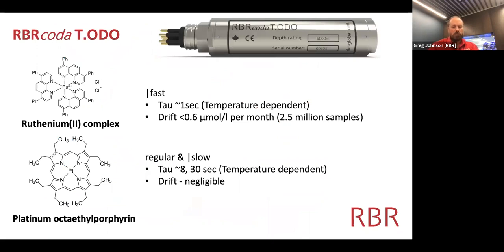So I'm going to draw your attention to the second grouping first. What is this luminophore? Well, this is a porphyrin complex. It looks a bit like a benzene ring. And this is the one that we use in the foil for the regular and slow coda. Those have 8-second and 30-second time constants. The drift on this foil, that is to say the change in behavior with the passage of time, is very low, and so it's well suited to mooring deployments. You can also correct it with 1 or 2 point calibrations.